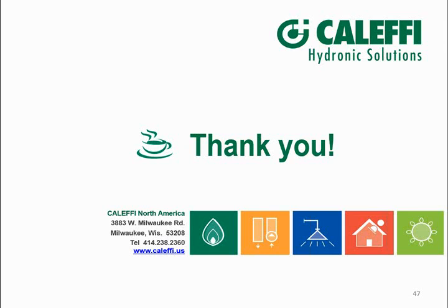Got it. Back to diaphragm-type tanks, and I'm not sure if you addressed it, I had to step out, but as it relates to the quality of the air that a tank is filled with, are there any issues or best practices as it relates to the type and quality of air? The air side of things really varies from manufacturer to manufacturer. Reading through some of the manuals, I've seen one say you can adjust the pre-charge with a bicycle pump, and on the other extreme, they recommend that you charge the tank with either nitrogen or air that's been dried through a desiccant tower.